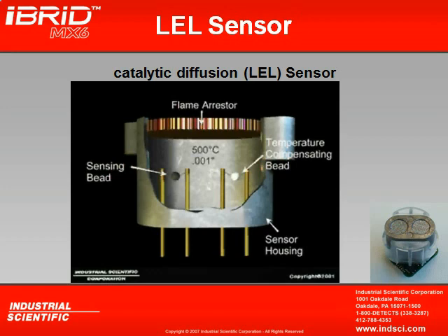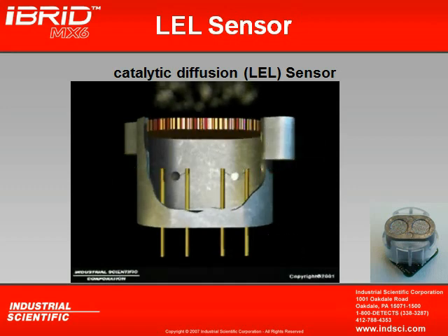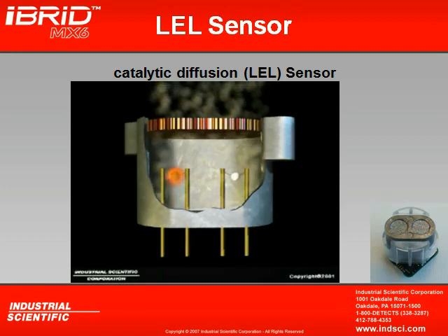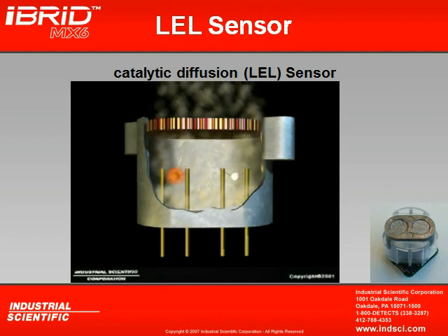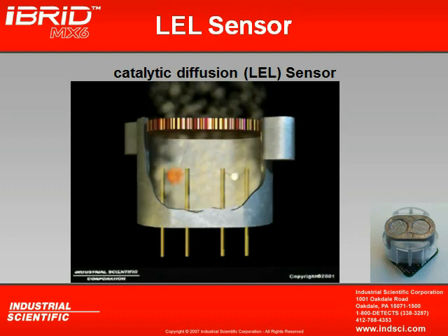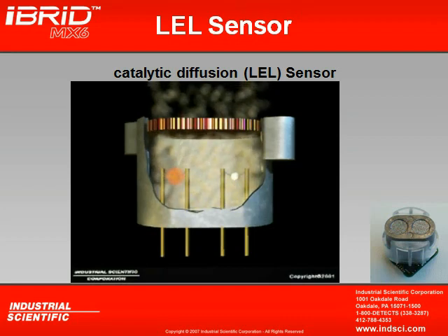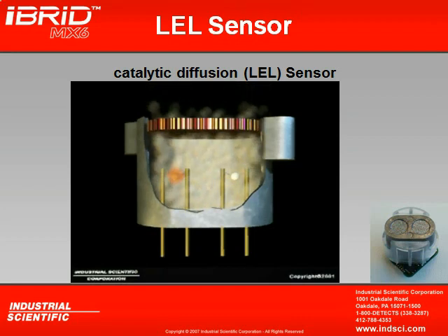Now when your sensor's plugged into the instrument and the instrument's turned on, these two little beads get up to 500 degrees Celsius, which is smoking hot. So when combustible gas vapors do enter into the sensing chamber, your sensing bead will start to physically burn the gas. So now I have one bead that's burning combustible gas, and I have another bead that's not burning combustible gas. What we know is that the sensing bead is going to be hotter. Whereas your temperature compensating bead may be staying at its 500 degrees Celsius reference point, your sensing bead may be 600 degrees Celsius. Alright, so now I have a 100 degree temperature difference between the two beads.